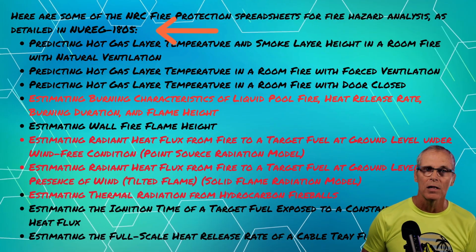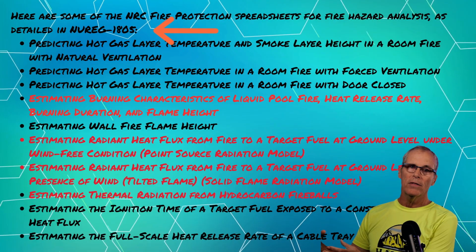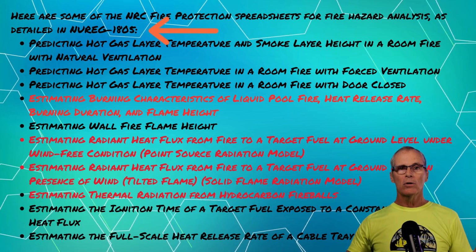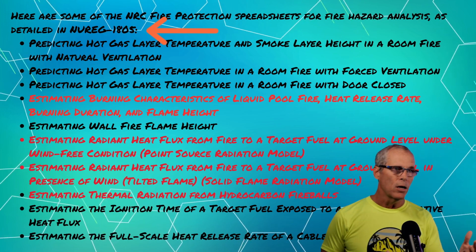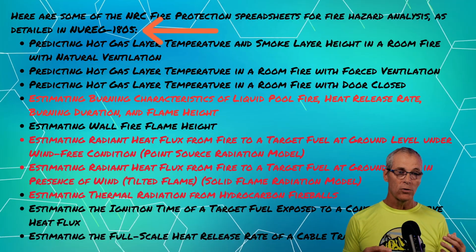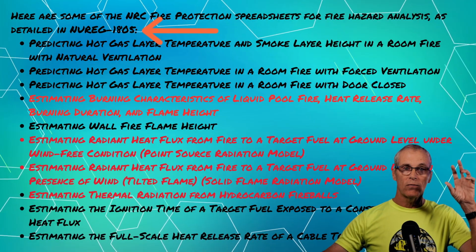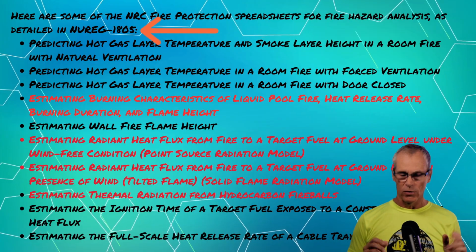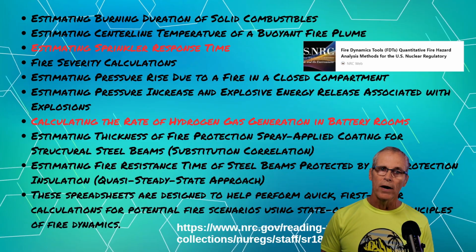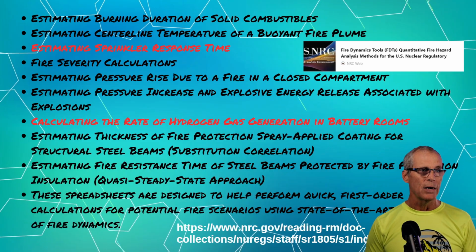How long is the fire going to last? If we spill the liquid out of this tank and it can fill this room, how long is that fire going to last? We can do the radiant heat flux from a pool fire and determine, will this tank be exposed from the radiant heat from this tank? So it's phenomenal. The website or the tools are called Fire Dynamics Tools. The site's down there at the bottom.